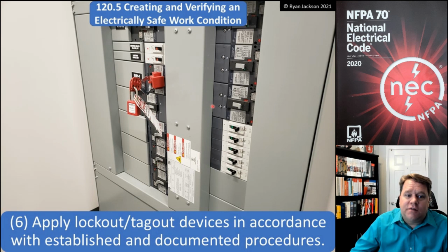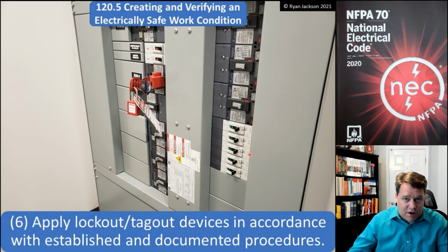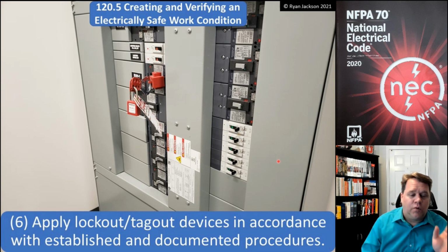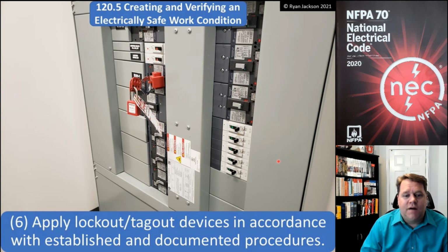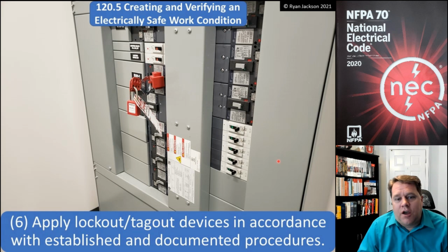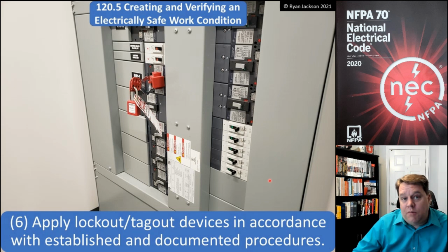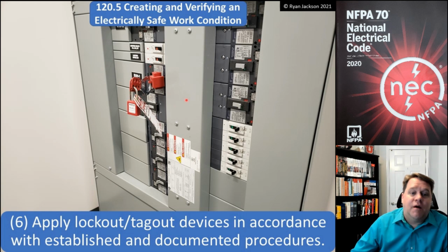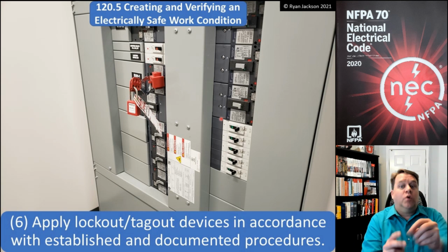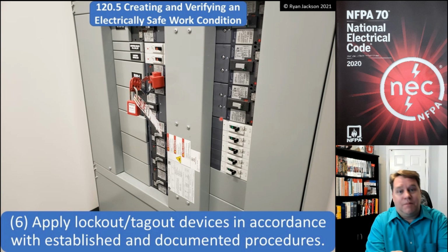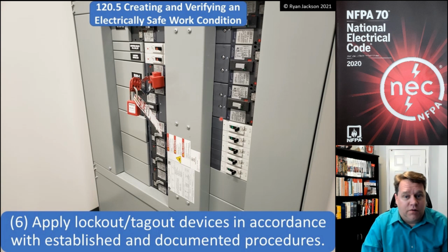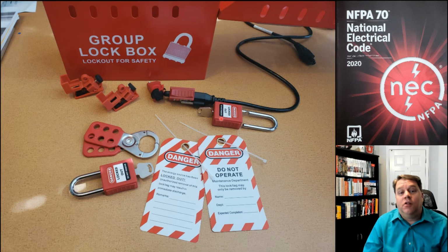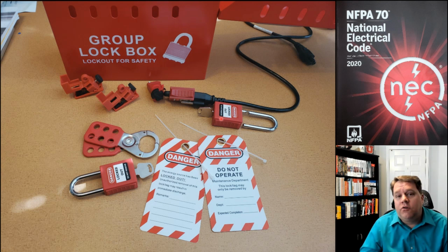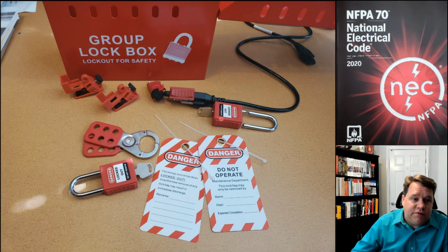So here in the photograph, we have a lockout and a tag. So this is not locked out and tagged out. It's got a lockout and it has a tag. So we're going to apply lockout or tagout devices in accordance with established and documented procedures. And part of the documented procedures is we're going to be using a lockout whenever possible. The only time I would use a tagout, hopefully, is when the design of the equipment wouldn't allow me to put a lock on it. Then you might have to resort to using a tagout device. So we need to have a lockout tagout program as part of our overall electrical safety program.